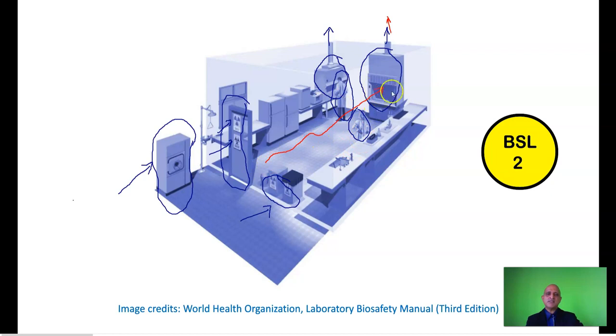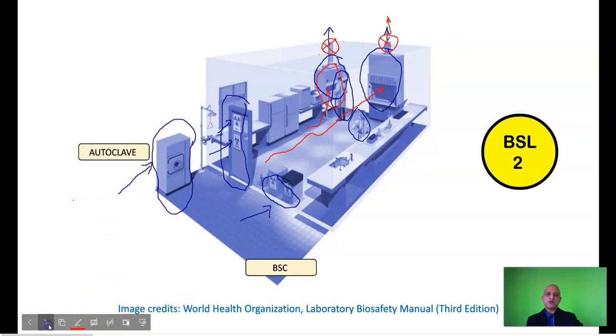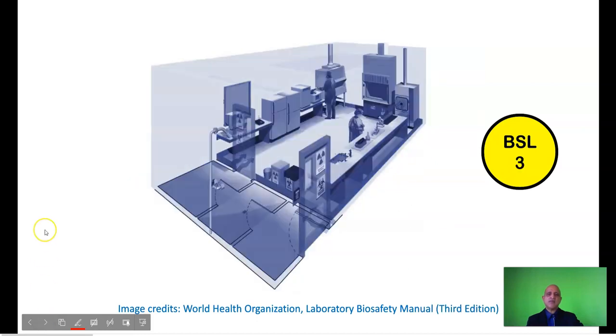The placement of this fume hood is very important. It's located at the end of the lab, far end, and basically everything is drawn into this fume hood and out. There is also over here a biological safety cabinet which has its own ducting. So all the air will be drawn into this cabinet and released into the environment, of course via a HEPA filter, because this affords the secondary level of containment. So that's basically a BSL2 setup which you can adopt to your specific laboratory. Okay, so this is the autoclave, the biological safety cabinet, the fume hood, and we move on to BSL3 now.